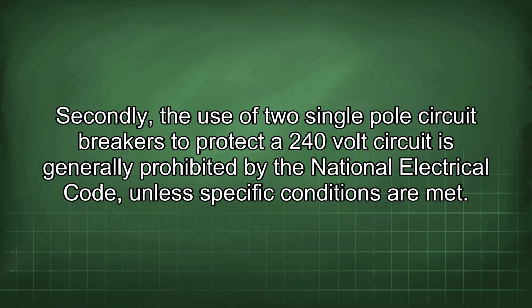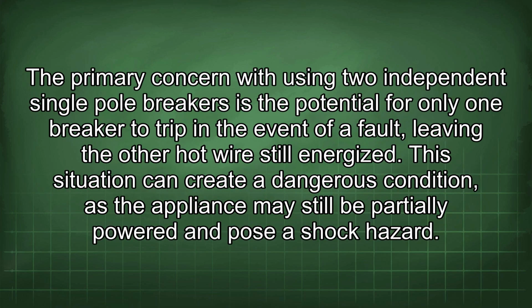Secondly, the use of two single-pole circuit breakers to protect a 240-volt circuit is generally prohibited by the National Electrical Code unless specific conditions are met. The primary concern with using two independent single-pole breakers is the potential for only one breaker to trip in the event of a fault, leaving the other hot wire still energized. This situation can create a dangerous condition, as the appliance may still be partially powered and pose a shock hazard.